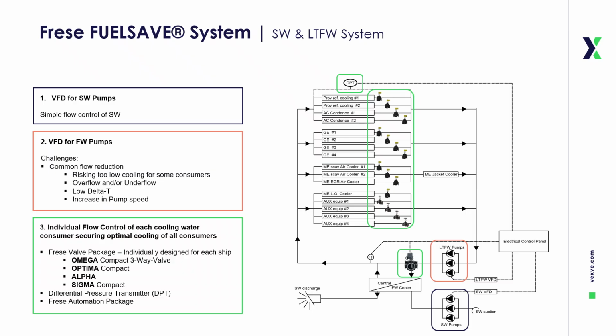This part introduces some challenges that need to be addressed by letting the pumps fluctuate in pressure without managing the flow for the individual consumers. We introduce a risk of starvation of individual consumers, overflow in parts of the system that causes a low delta T. 3. To overcome these risks, we introduce individual flow control of each cooling water consumer, securing optimal cooling of all consumers.